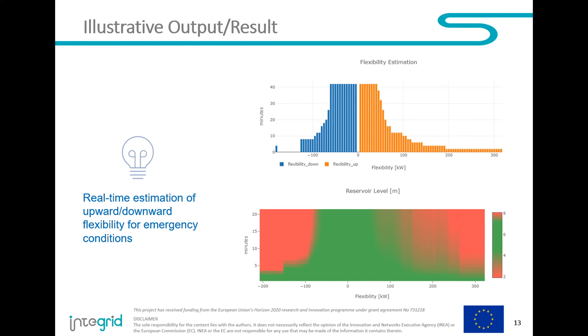This is a real case study in the Integrid project for a wastewater station. An operator can see from the plot that, for example, 200 kilowatts can be cut for less than 10 minutes — very important information in an emergency situation requiring load shedding. The operator knows exactly how much flexibility is available and for how long. That is the concept we are exploring in Integrid: giving human operators information about flexibility for industrial processes.